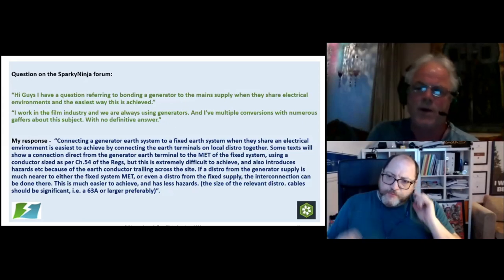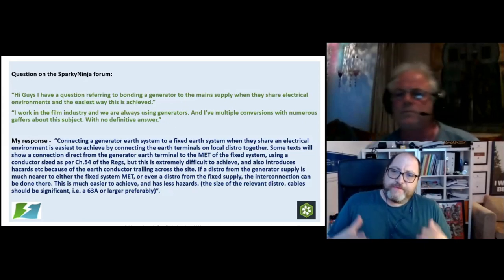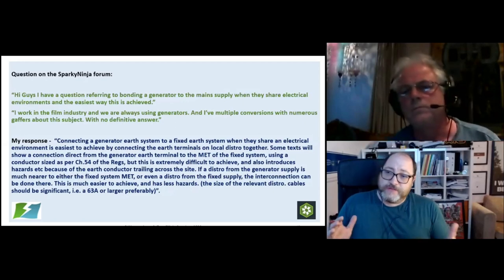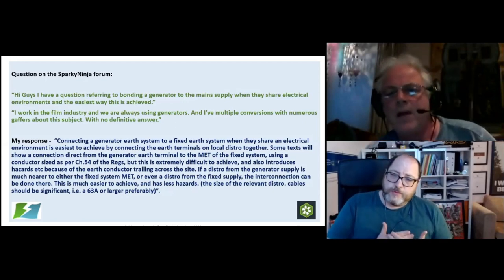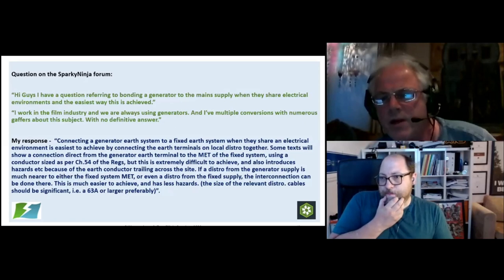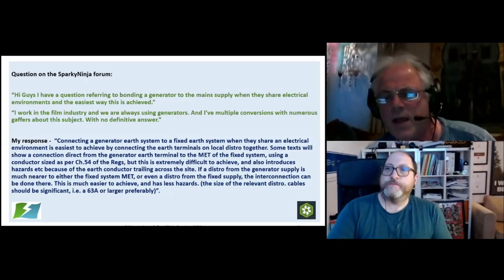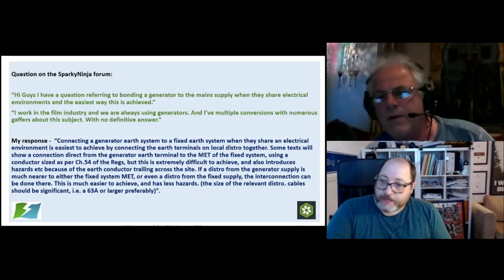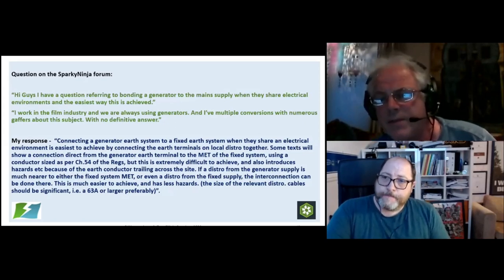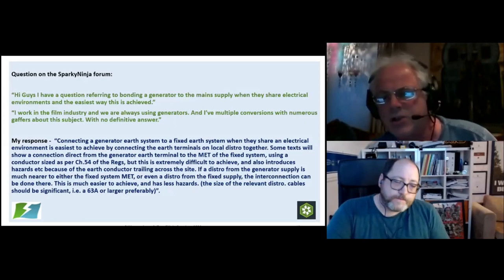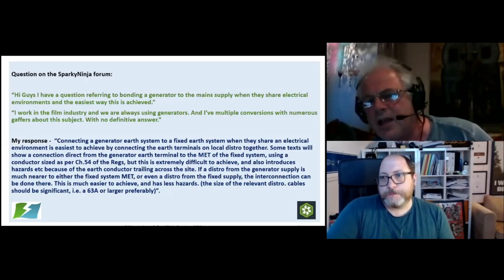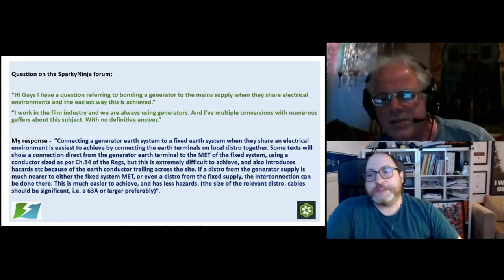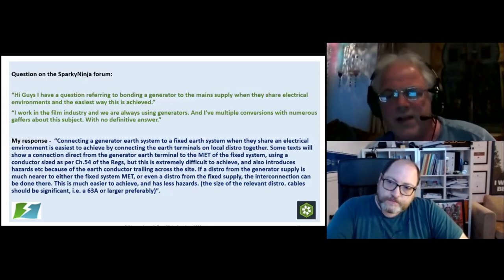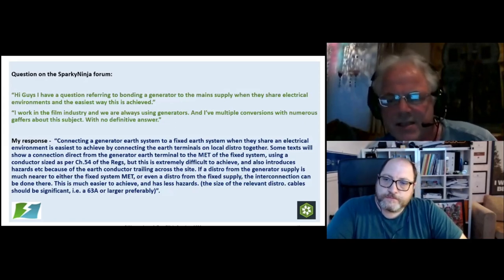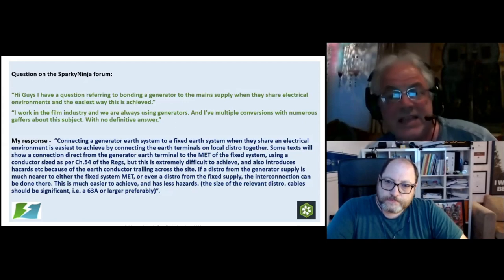But is this only a problem if users or maybe livestock could come into contact with the two environments? Well, if you're going into a building, remember that you're going to have electrical equipment coming off the generator supply, and within the building you're going to have electrical equipment and the bonding and various other bits and pieces which are connected to the fixed installation. Now the fixed installation is going to have its own earthing system, which is going to be connected to the transformer earth electrode, whether it's a TNS or a TNCS. Or if it's a TT, it's going to have its own external electrode in the building.